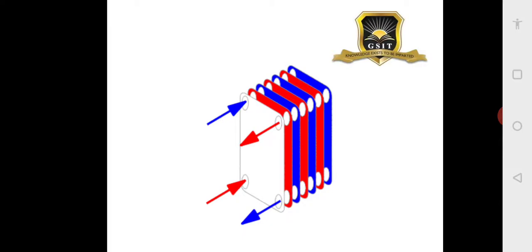Now coming to plate type heat exchangers — these are very thin plates and the gap between the plates is also very small, around 1.3 to 1.5 mm. In between the plates, alternately you will find the hot fluid and the cold fluid, so there are alternate layers of hot and cold fluid.